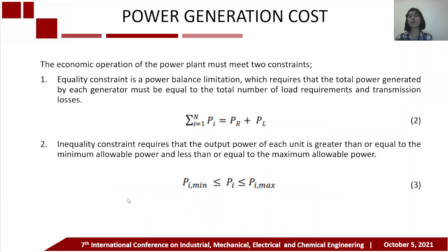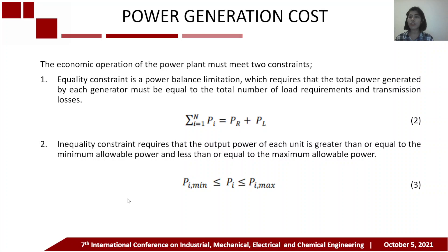The economic operation of the power plant must meet two constraints. First, the equality constraint, which is the power balance limitation requiring that the total power generated by each generator must equal the total load requirement and transmission losses, expressed by equation 2. Second, the inequality constraint requires that the output power of each unit is greater than or equal to the minimum allowable power and less than or equal to the maximum allowable power, expressed in equation 3.